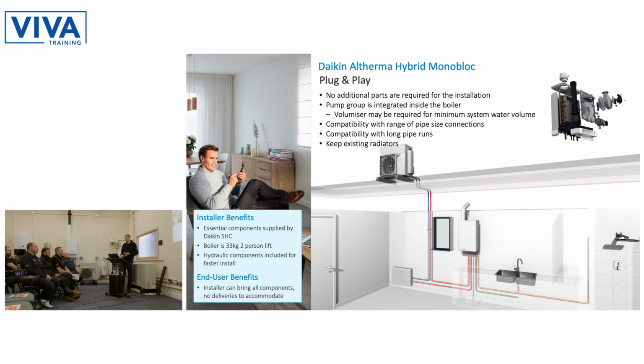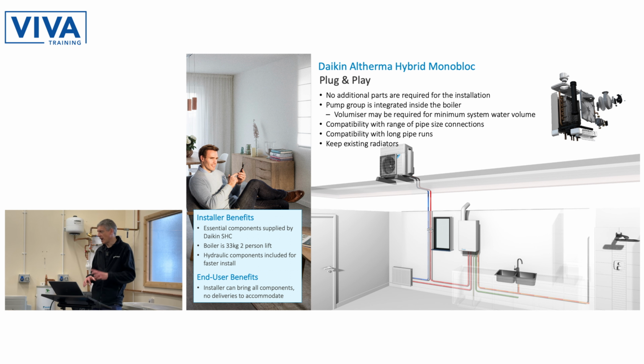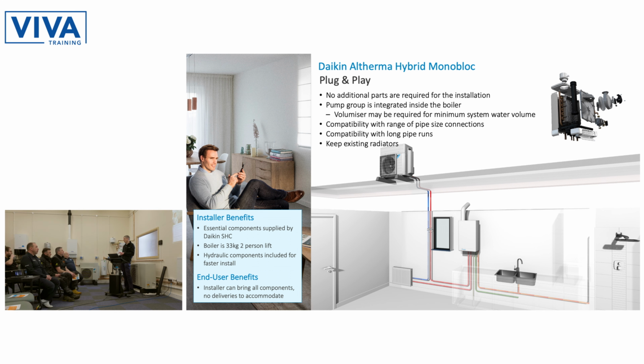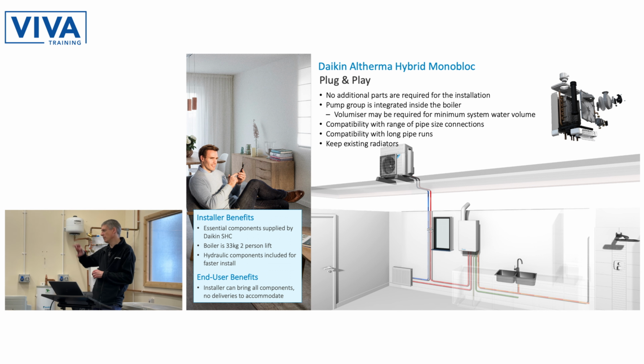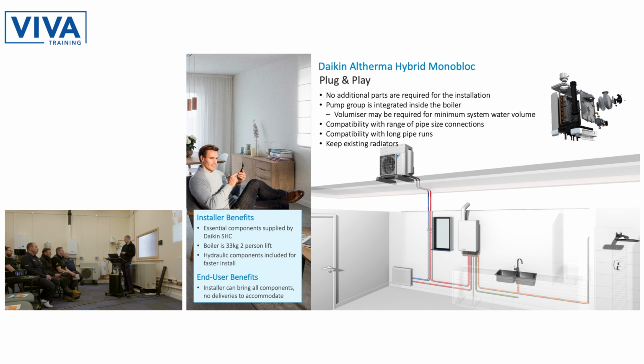55. So once you've got... Although you can go above 55, the heat pump will take it up to 55, and then the boiler will take it up a little bit further. So just because you need to go over 55, you're not necessarily ruling out the heat pump operating at all, but it really depends what return temperature then comes back. If you're really boosting it up with a boiler and it doesn't come back low enough for the heat pump to continue to operate, then yes, you will be outside the operating range of the heat pump. But you can go higher than 55 with the heat pump still operating as long as the return temperature is coming back low enough for it to keep working.